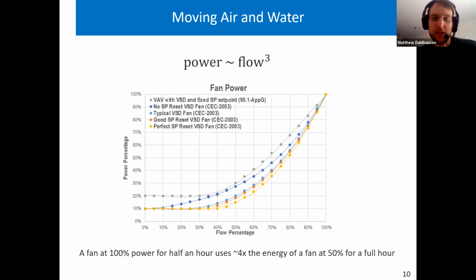Many HVAC systems, especially residential ones, are cycling systems, meaning we turn on for a while until the set point is reached and then turn off. Let's say we have a fan that can either cycle on and off at 100% of flow for a total working duration of half an hour, or operate at 50% capacity for the full hour. It moves the same amount of air in both cases, but uses 4 times more energy over the hour when it's in cycling mode.